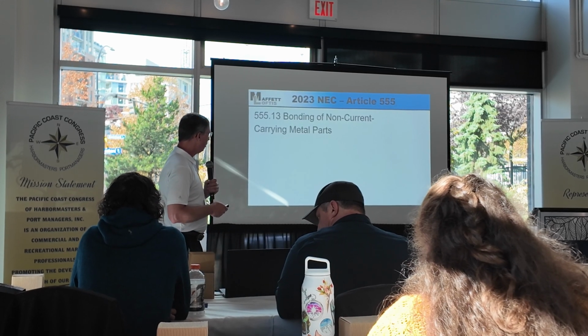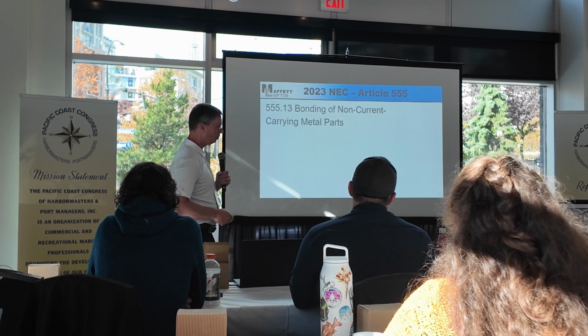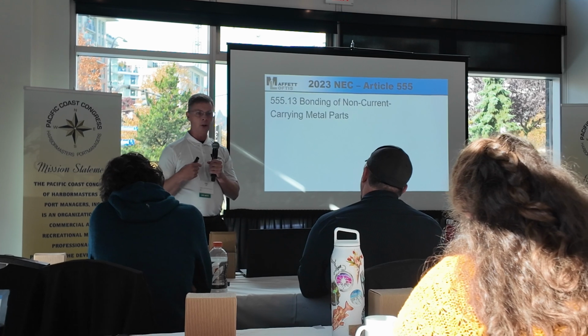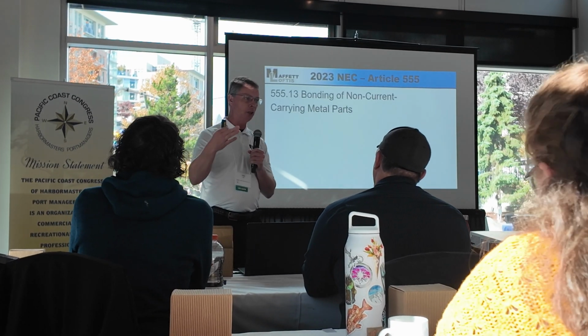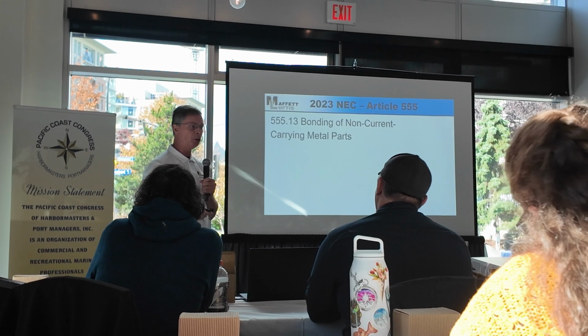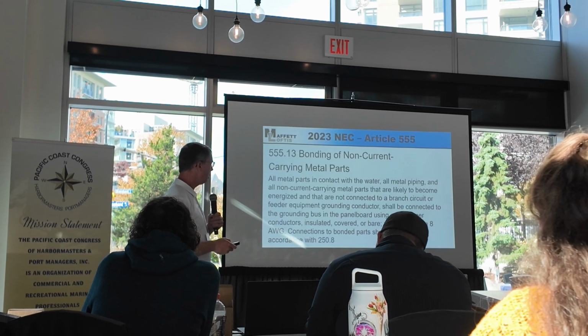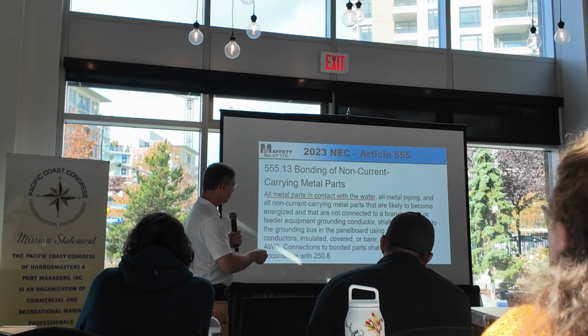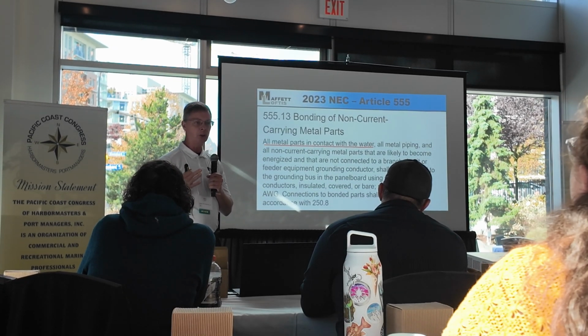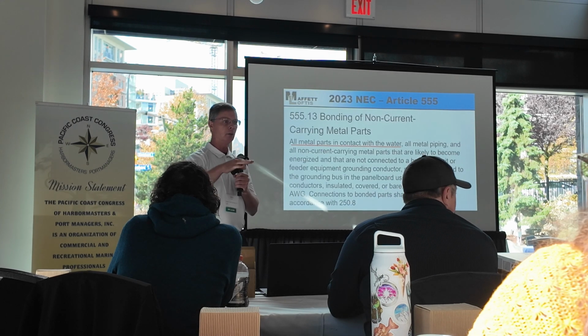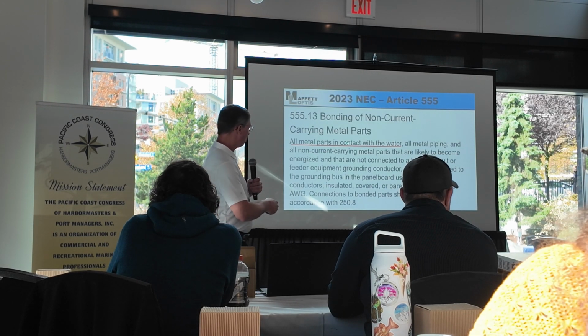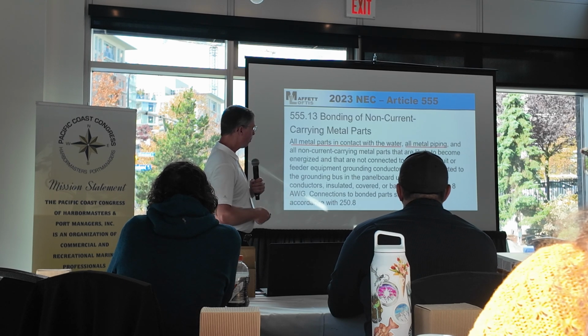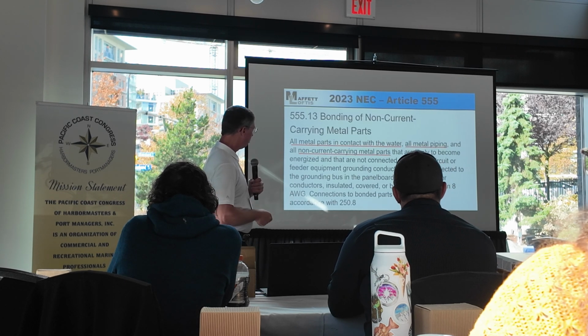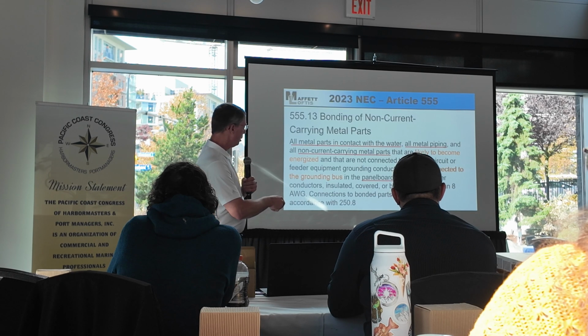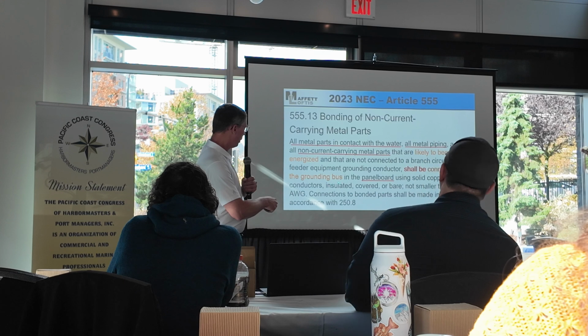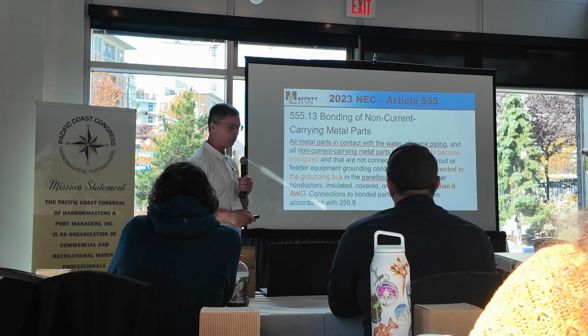But bonding of non-current carrying parts, I'm going to go back to 2023 because, like I said, 13 states are adopting 2023 or have adopted 2023, and there's 10 more adopting. Electrical inspectors have misinterpreted what the intent of the code making panel does. If you look at this code, basically it says all metal parts, and there's a list of 3 items that have to be bonded, which is basically just connecting it to a wire so they're all at equal potential, so all the same voltage. But there's a list: all metal parts in contact with the water, all metal piping, and non-current carrying metal parts. And the trick is that what's likely to be energized shall be connected to the grounding bus of the panel with a wire not smaller than number 8.